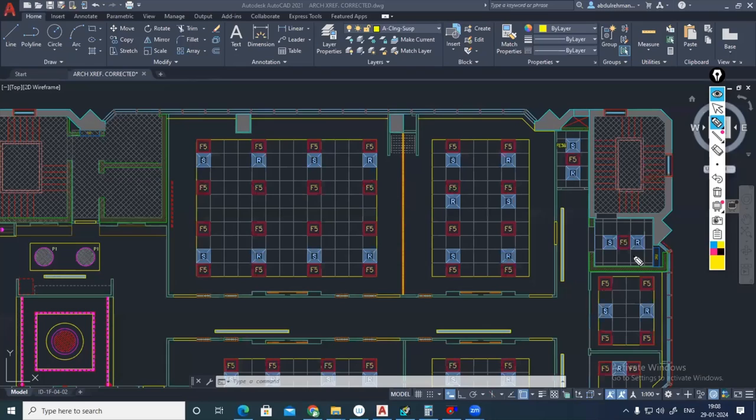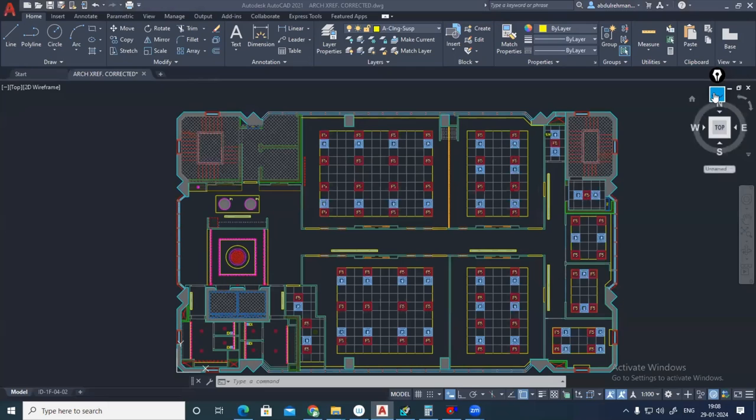Where will I place it? When we are placing the machine, the cooling medium also has to be considered. In this building, it's a five-story building, ground plus four only. We are having ground, first, typical floors, then until the roof level. So the ton of refrigeration will come to just less than 200 ton only. So a VRV, VRF machine is sufficient here.